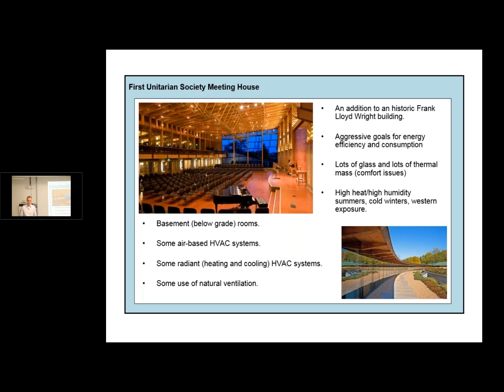The systems were very different. The Unitarian Meeting House building had a little bit of HVAC by means of air, meaning blowing hot air and cold air into the space to keep it comfortable. But the large majority of the thermal loads were taken up by radiantly heated floors and radiantly cooled floors - concrete floors with piping in them. It's kind of a no-brainer thinking about how to do hot radiant floors, but cold radiant floors can get you into trouble if condensation becomes a concern, and it certainly was.